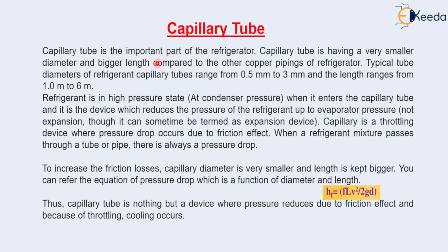The capillary tube is an important part of a refrigerator. It has a very small diameter and a bigger length compared to other copper piping in the refrigerator. Typically, the diameter of refrigeration capillary tubes ranges from 0.5 mm to 3 mm, and the length ranges from 1 meter to 6 meters.